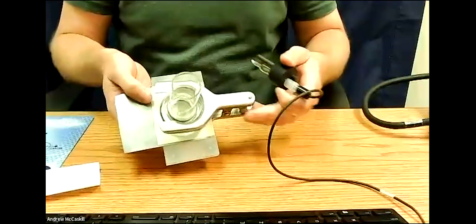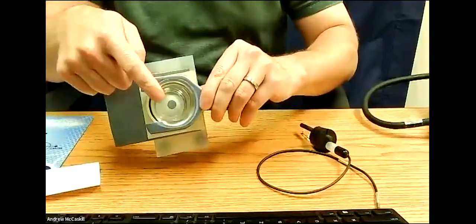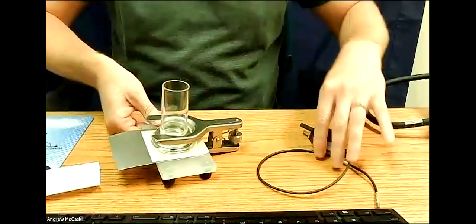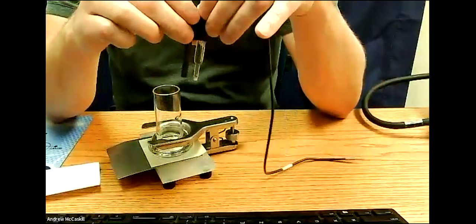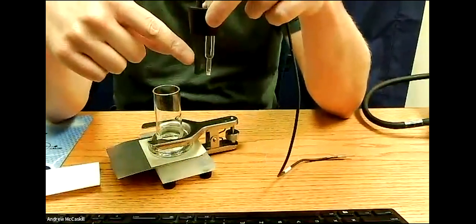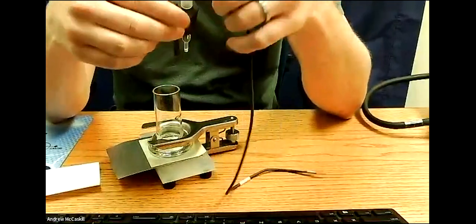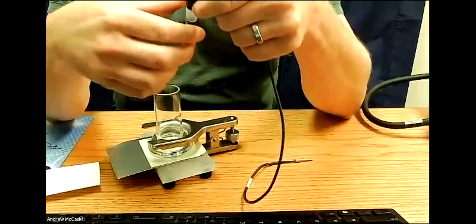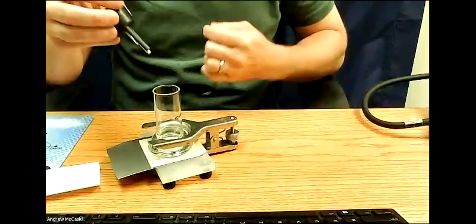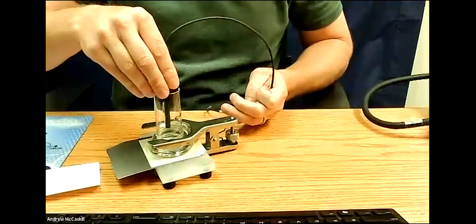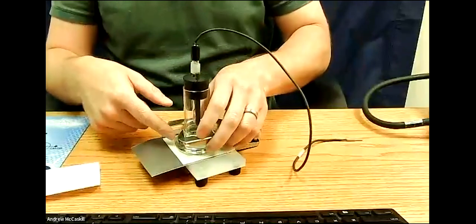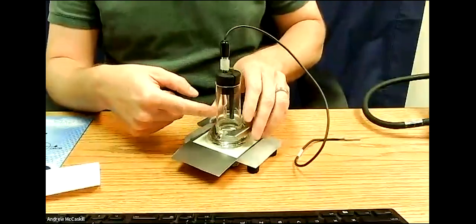So this is my working electrode right here. It's my sample. That's the exposed area of the working electrode. And I have my counter electrode right here. It's just a graphite rod. I have my reference electrode right here. This one is actually a silver chloride, but in the cell I'm using, I have a calomel reference electrode. This sits in the top. You would fill this up with solution up to the point.